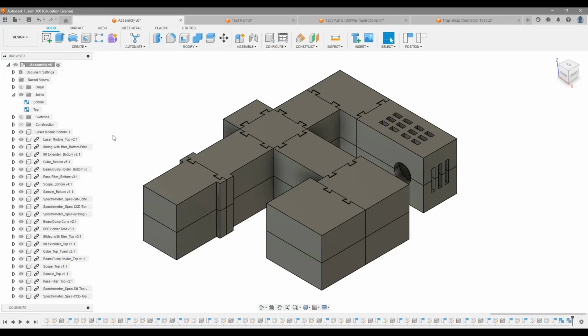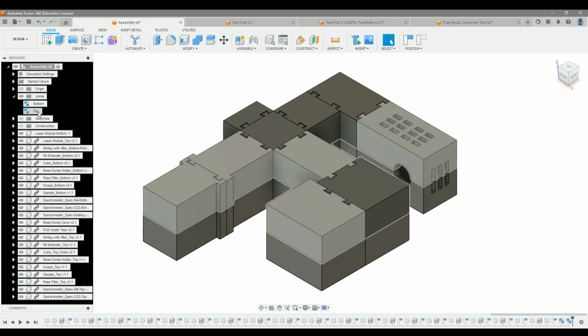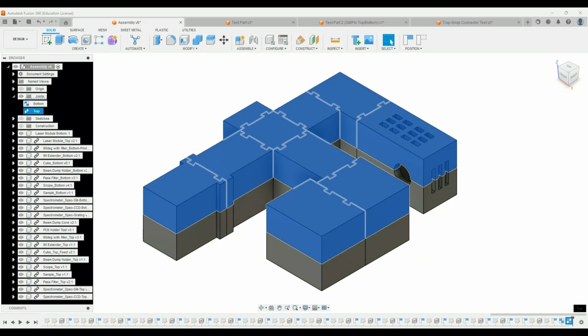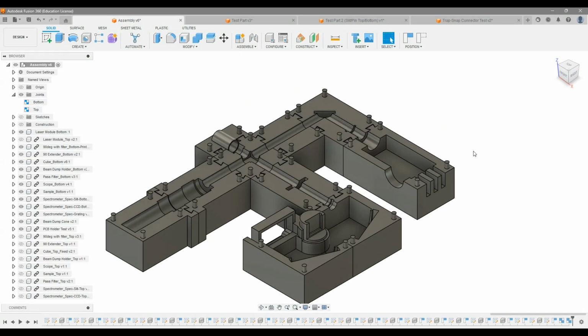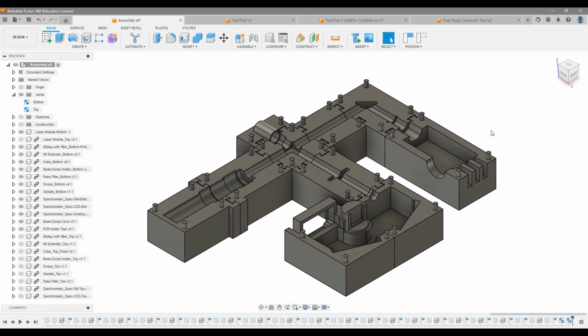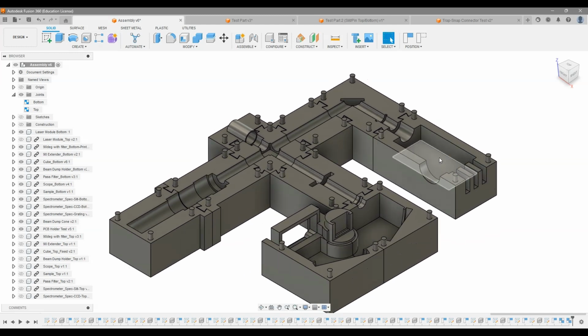Okay, so this is the CAD model for the Raman Spectrometer design. If I go ahead and hide the top of it, you can see the internals and where each individual component will be sitting. So here we have the laser module, which is the source of the light. It initially passes through a 532 nanometer bandpass filter to ensure that only the green light is entering the system, and then turns 90 degrees via a flat surface mirror.